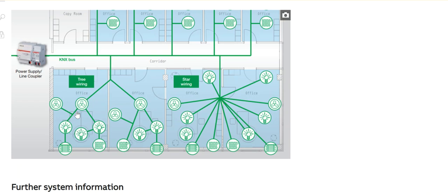So what it brings for us is that we can reduce the KNX wiring in a building. For example, if you use star wiring, you should spend so much wire, okay? So in a server-based system, in the centralized system in B4, they only use star wiring. For example, if you want to configure the RTI from USA, you should use star wiring, okay? So it requires so much wiring. But if you use the tree, okay, you can go out from the electrical cabinet to the first sensor, and then to the next sensor, and then to the next sensor.